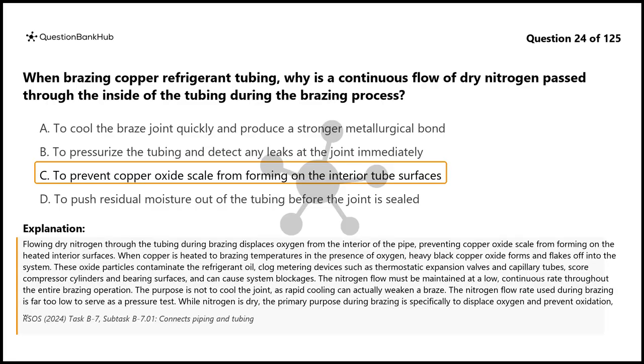Flowing dry nitrogen through the tubing during brazing displaces oxygen from the interior of the pipe, preventing copper oxide scale from forming on the heated interior surfaces. When copper is heated to brazing temperatures in the presence of oxygen, heavy black copper oxide forms and flakes off into the system. These oxide particles contaminate the refrigerant oil, clog metering devices such as thermostatic expansion valves and capillary tubes, score compressor cylinders and bearing surfaces, and can cause system blockages.